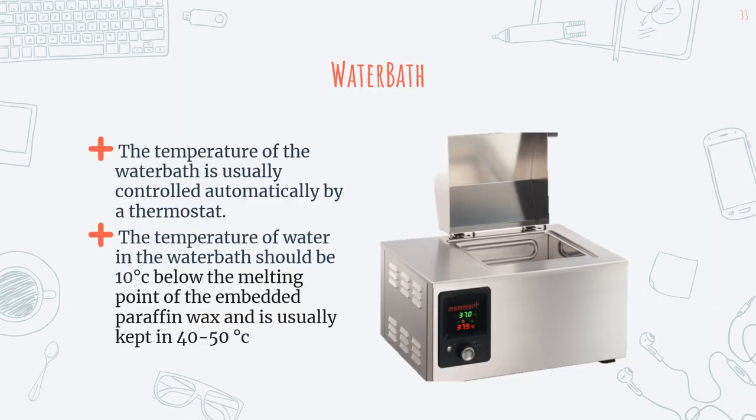The water bath temperature is usually controlled automatically by a thermostat. The temperature of the water should be 10 degrees Celsius below the melting point of the embedded paraffin wax, and is usually kept at 40 to 50 degrees Celsius.